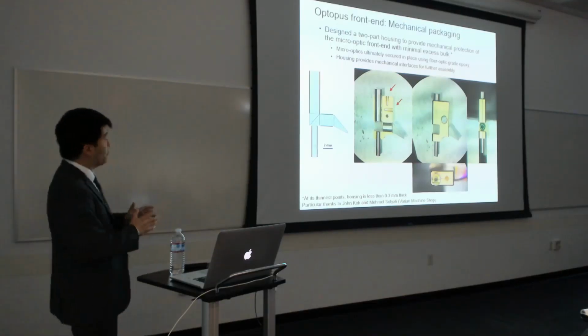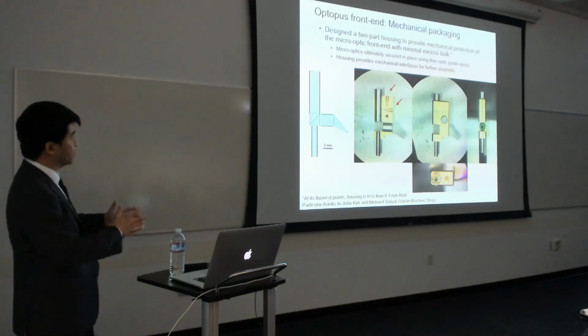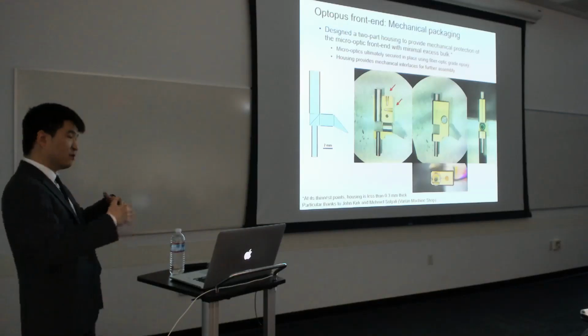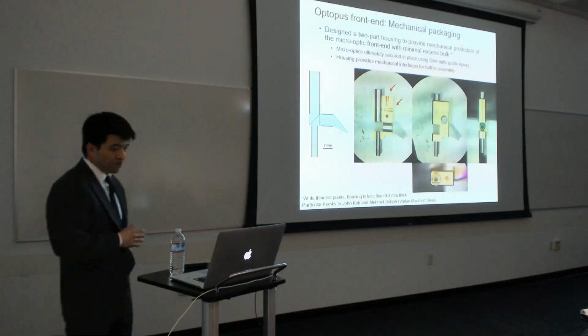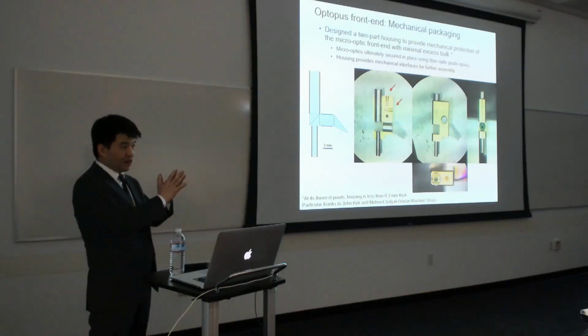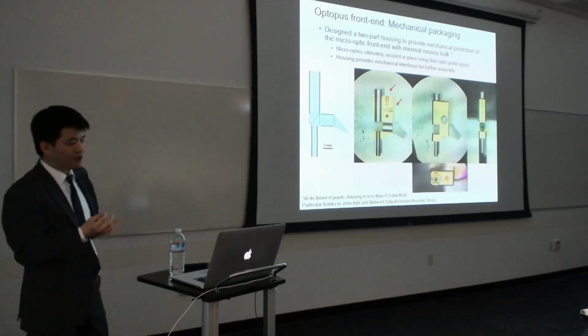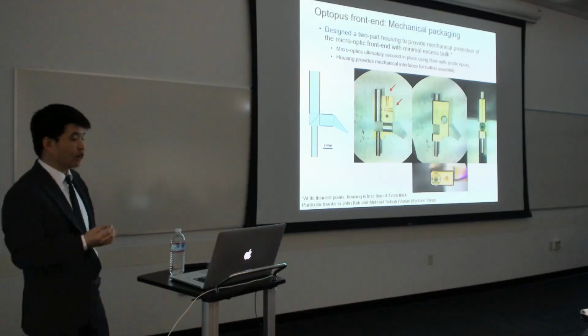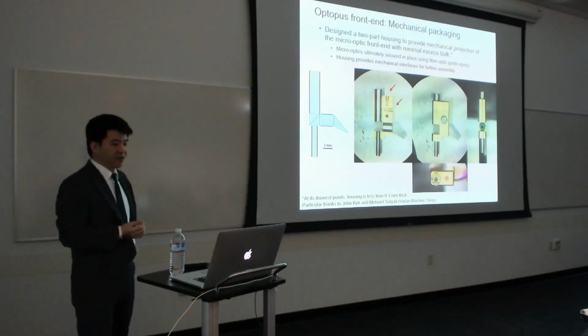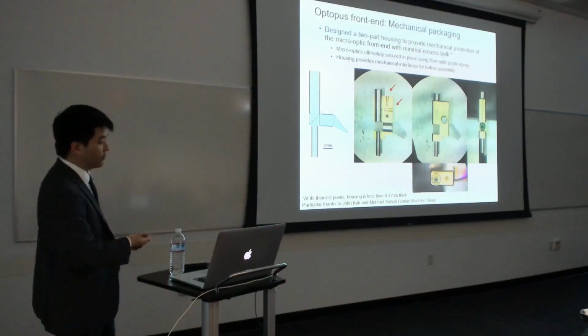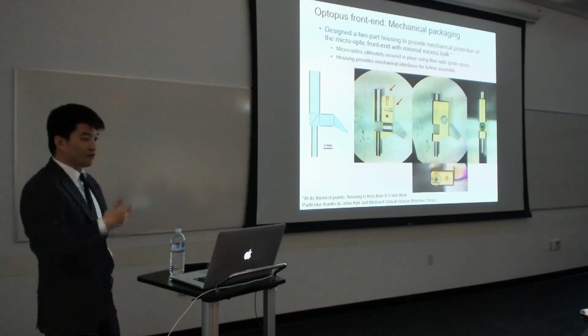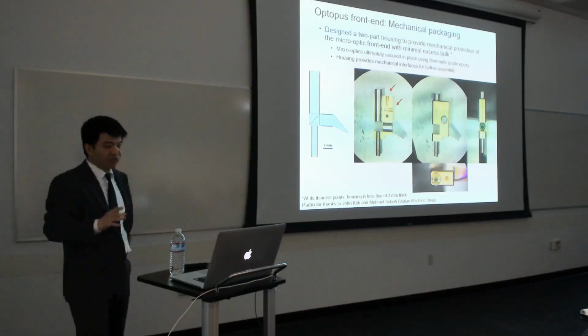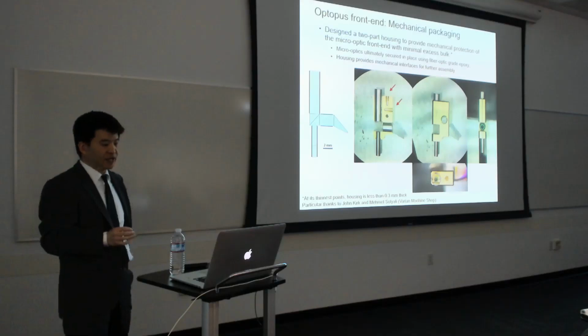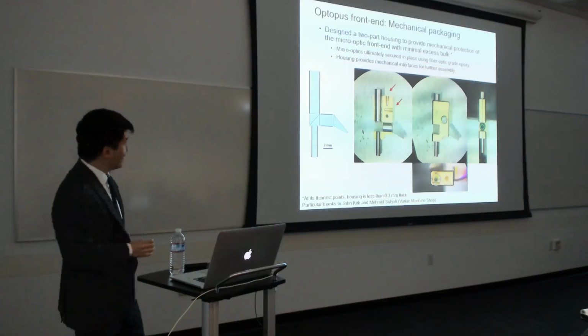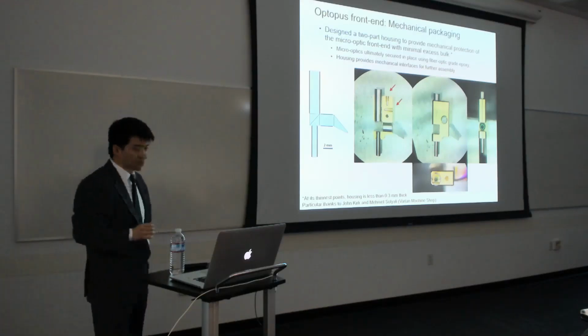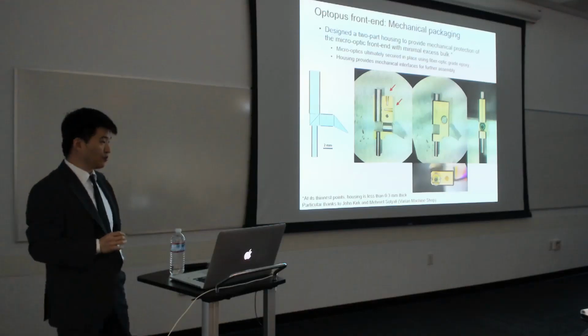We designed a 2-part housing to provide mechanical protection of the micro-optic front end with minimal excess bulk. The 2 parts clasp onto the micro-optic assembly, and we secure the optical elements internally by using a fiber-grade epoxy. Additionally, the housing provides additional mechanical interfaces, which are indicated in red for further assembly. And we're able to achieve all of this while adding very little excess bulk beyond the optical core. At the thinnest points of this housing material, the parts are less than 0.3 millimeters thick.